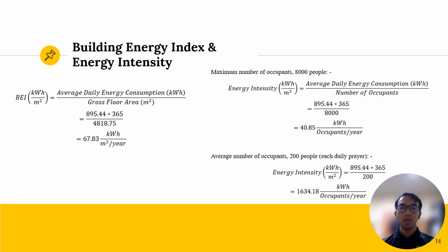This slide shows the calculation of current building energy index and also energy intensity. The building energy index is calculated by dividing the average daily energy consumption with the gross floor area of the mosque. The result obtained is 67.83 kWh per square meter per year. Meanwhile, the energy intensity is calculated by dividing the average daily energy consumption with the number of occupants in the mosque. The result obtained is 40.85 kWh per occupant per year if the mosque reached its maximum capacity, and 1,634.18 kWh per occupant per year if the average number of occupants is considered.